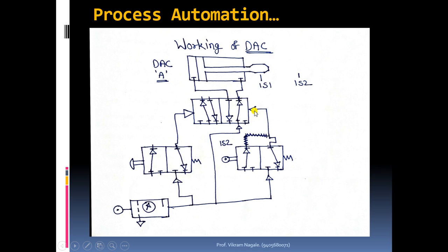Unless we apply pressure on the right hand side of this valve, this block will not change its status, because initially the pressure was on the left hand side. When we release this push button, the linings will get shifted to the right side block, and the air up to the left hand side of this valve has to exhaust into the atmosphere through the right side lining of the valve.